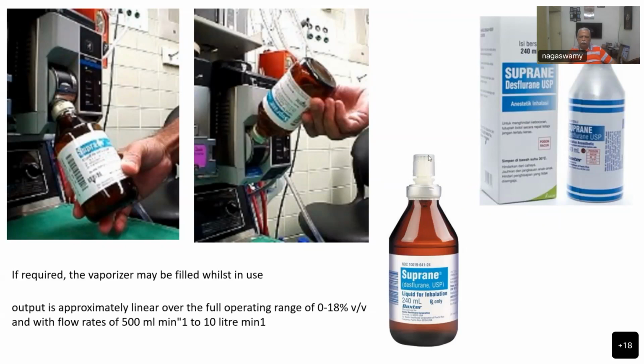So this filling port is sealed with the bottle, and you have to just insert it into the slot and press the bottle. Once you press, there is a spring which will get released, and the fluid will start flowing through that. And once it fills to the maximum, it will automatically stop flowing further, and overfilling or spilling cannot happen. So these are the few points that you would like to add to this particular topic.